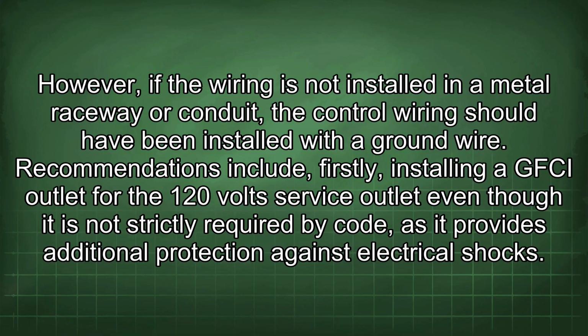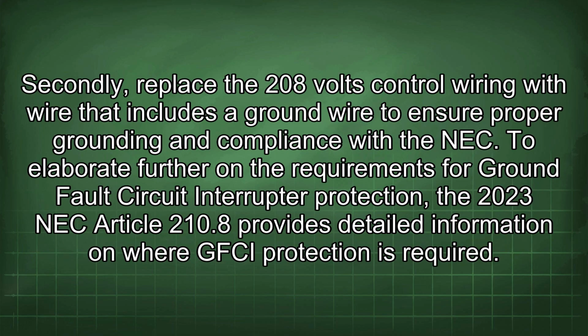Recommendations include, firstly, installing a GFCI outlet for the 120 volts service outlet even though it is not strictly required by code, as it provides additional protection against electrical shocks.